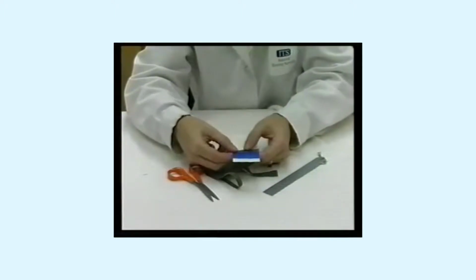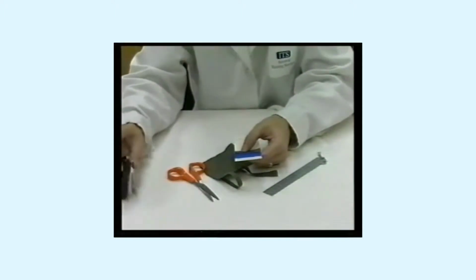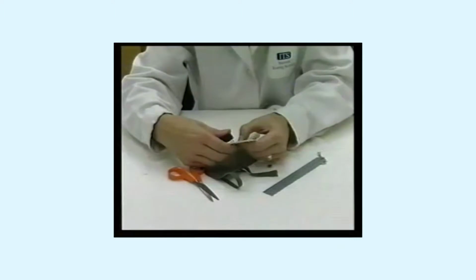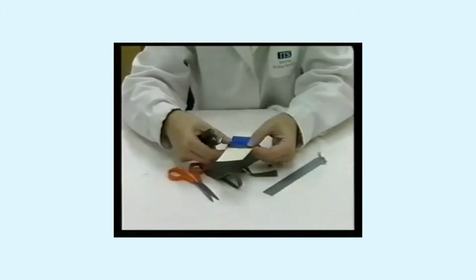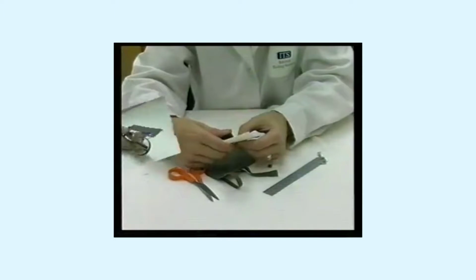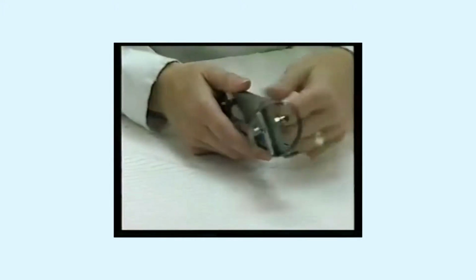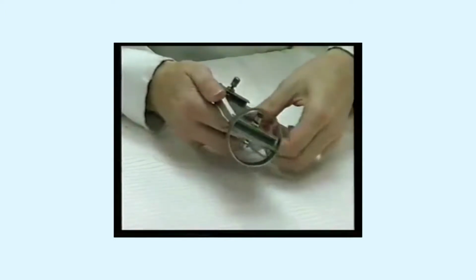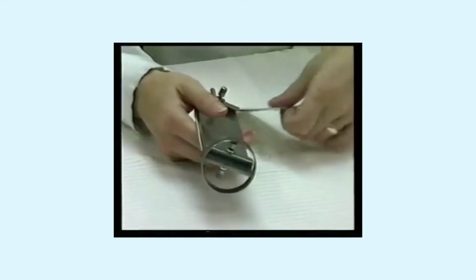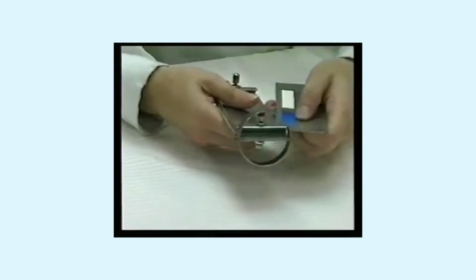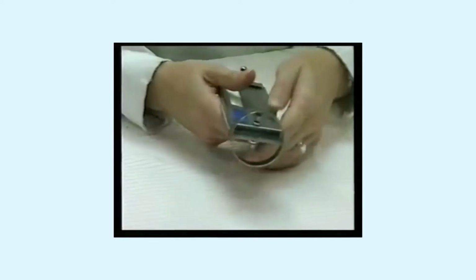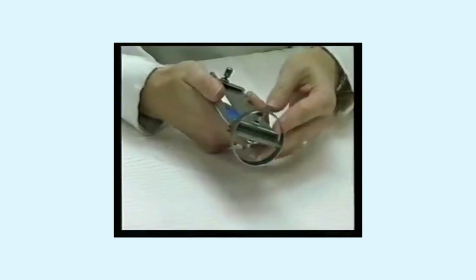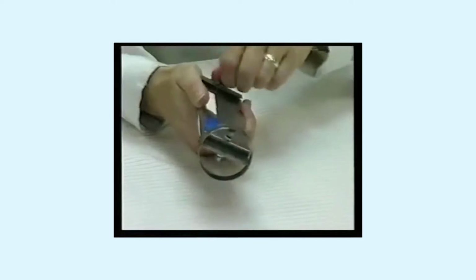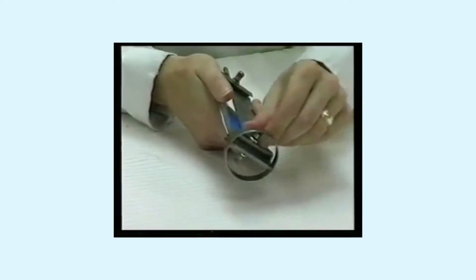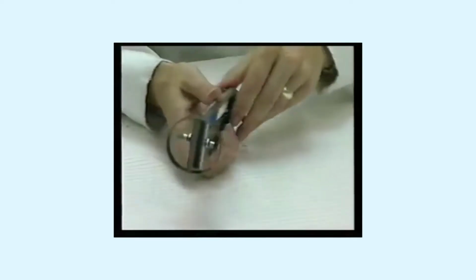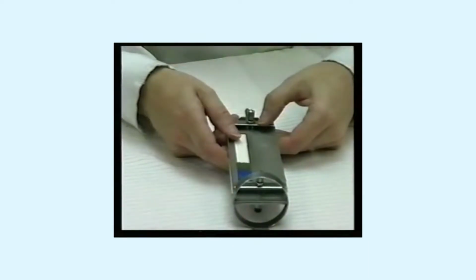The test specimen is mounted onto a special white card. The complete card is mounted into the specimen holders with an area of the test specimen covered by a metal mask. A similar card is prepared using similar sized strips of the blue dyed standards. The number used varies according to the performance standard required. Cards are mounted on each side of the holder.